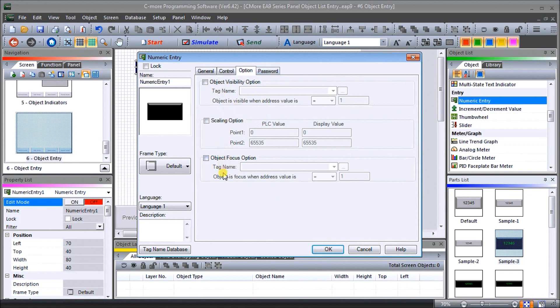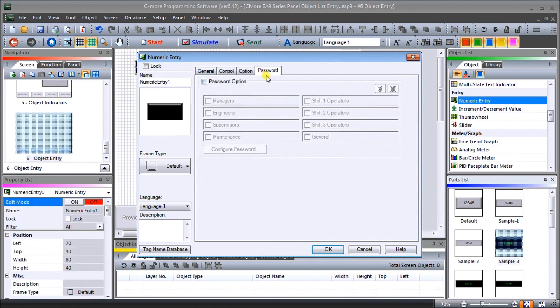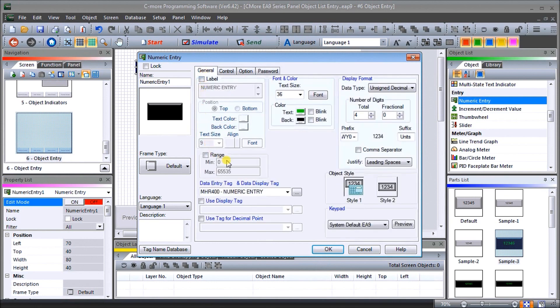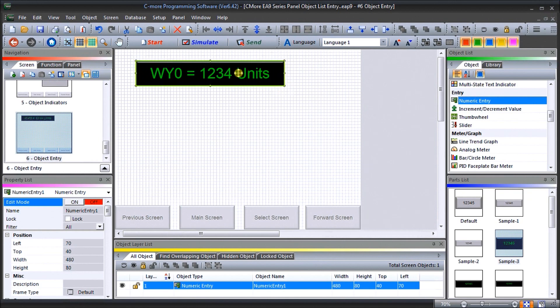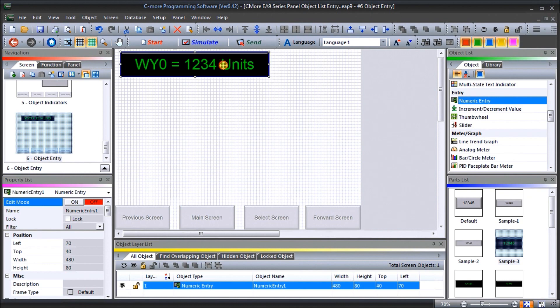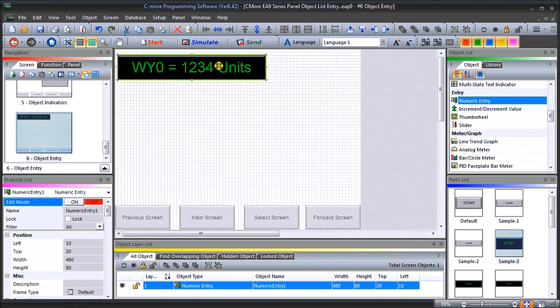Object focus means that when the screen is on it has focus for that individual item, which is required when using things like a barcode scanner. We have password which we won't set. Back on the general tab, under range, we'll set it to 0 to 4095 because WX0 is our analog display with a range of 0 to 4095 — we don't want to enter something outside that range. Hit OK and size the display to look good, then hit save.